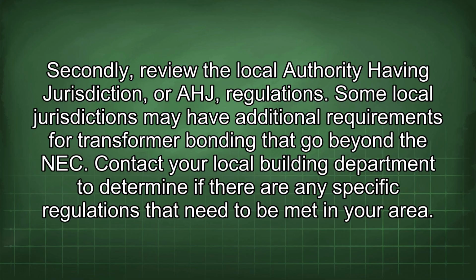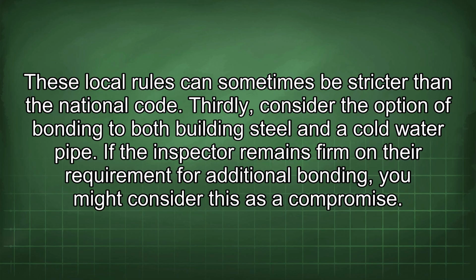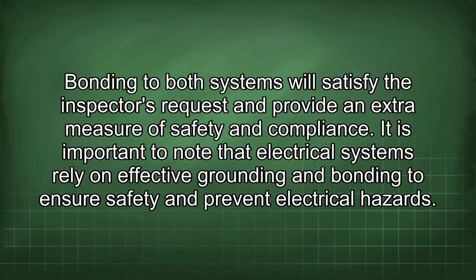Secondly, review the local authority having jurisdiction, or AHJ, regulations. Some local jurisdictions may have additional requirements for transformer bonding that go beyond the NEC. Contact your local building department to determine if there are any specific regulations that need to be met in your area. These local rules can sometimes be stricter than the national code. Thirdly, consider the option of bonding to both building steel and a cold water pipe. If the inspector remains firm on their requirement for additional bonding, you might consider this as a compromise. Bonding to both systems will satisfy the inspector's request and provide an extra measure of safety and compliance.